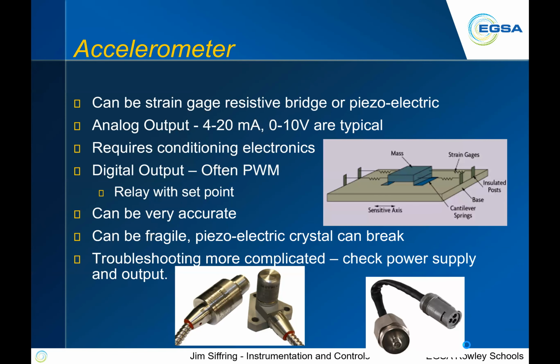Accelerometers can be a strain gauge, resistive bridge, piezoelectric, all that kind of stuff. Typically, they're using a 4 to 20 milliamp or a 0 to 10 volt output. 0 to 10 volts is very similar to 4 to 20 milliamp, but the 0 is 0, as opposed to 4. It requires conditioning electronics, so you almost always have to have some kind of a device that can take the signals coming off of here and convert them into something we can actually look at and use to go into our control system. But for digital outputs, often that conditioning electronics will give you a PWM signal.